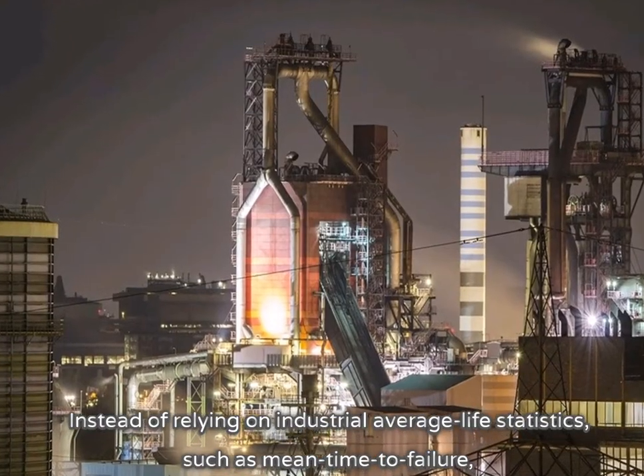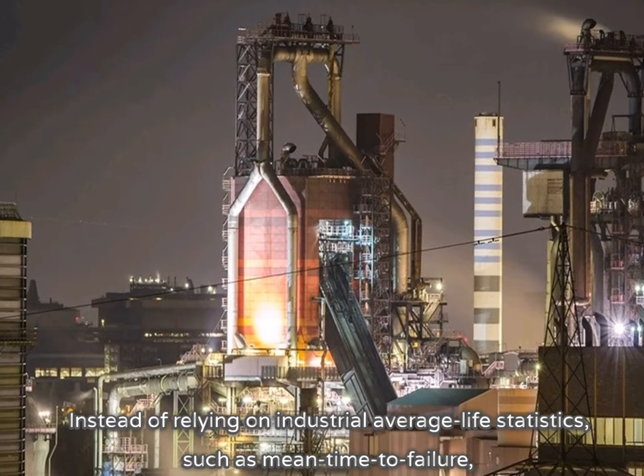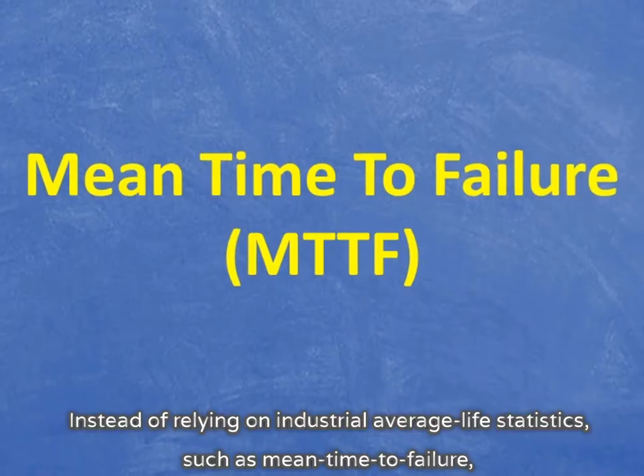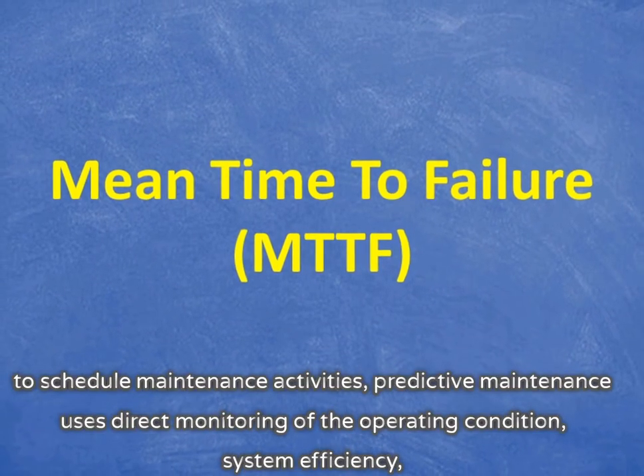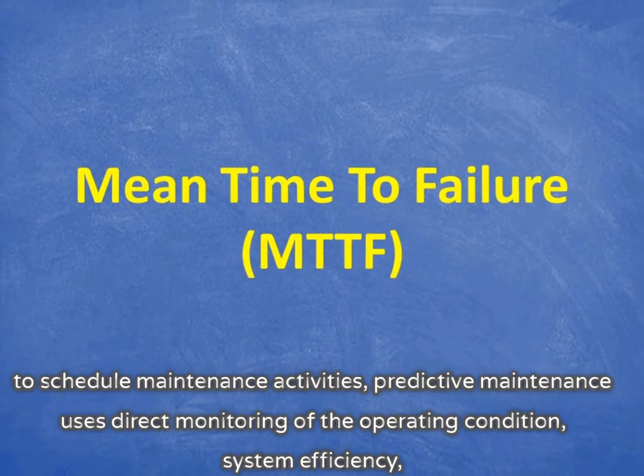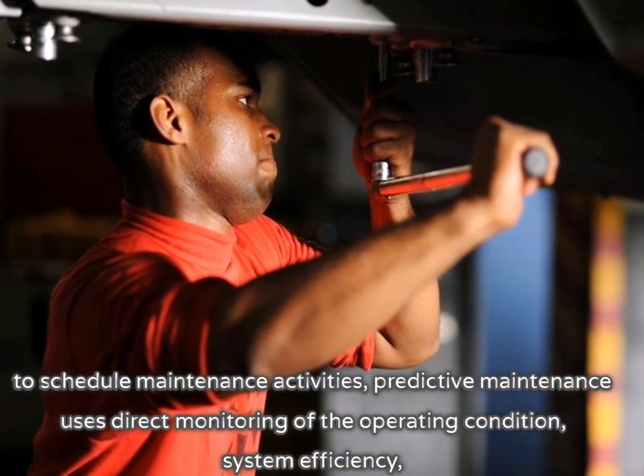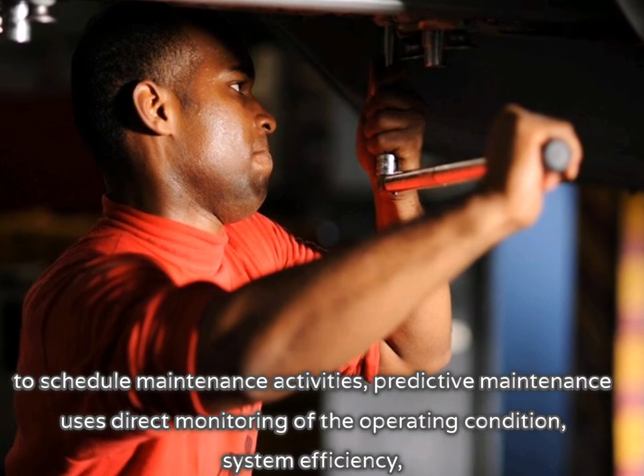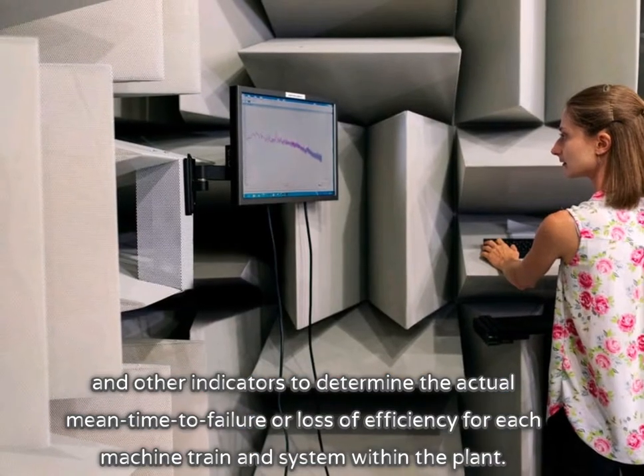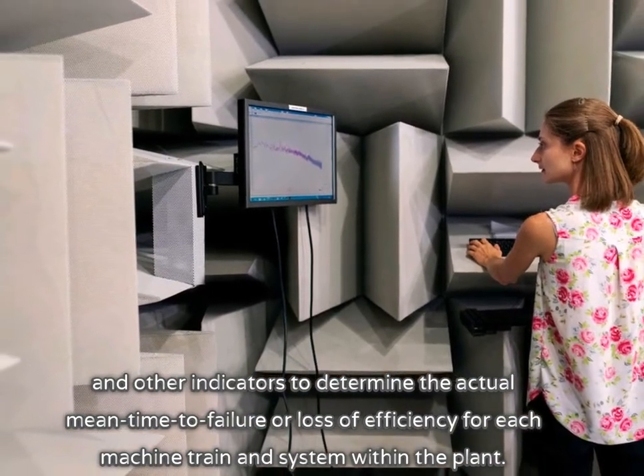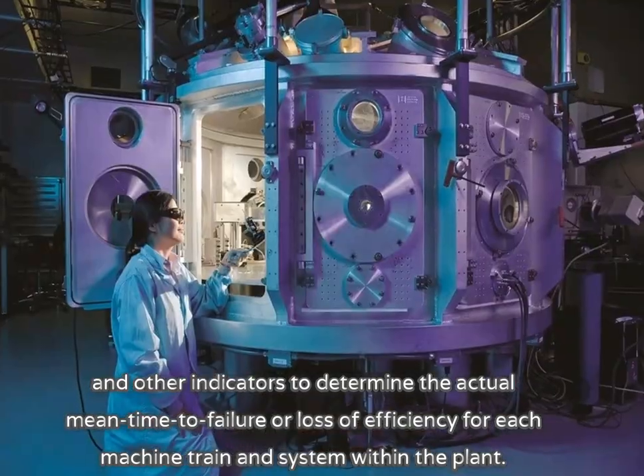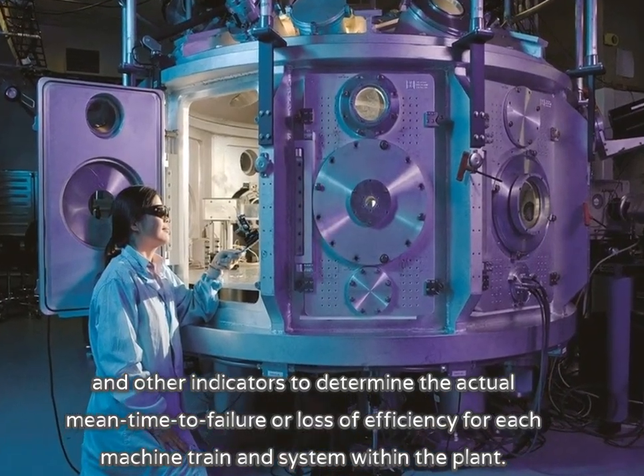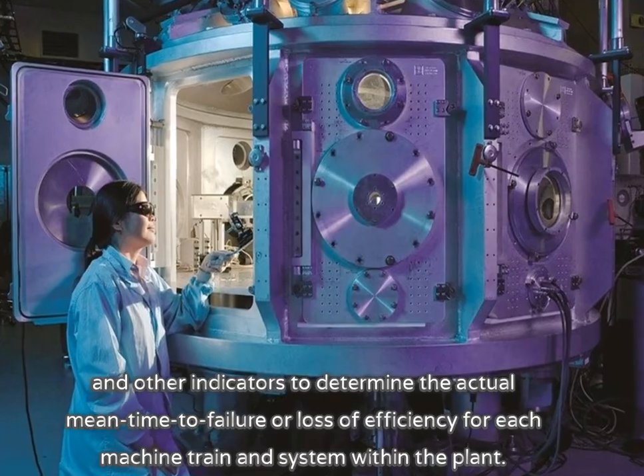Instead of relying on industrial average life statistics, such as mean time to failure, to schedule maintenance activities, predictive maintenance uses direct monitoring of the operating condition, system efficiency, and other indicators to determine the actual mean time to failure or loss of efficiency for each machine train and system within the plant.